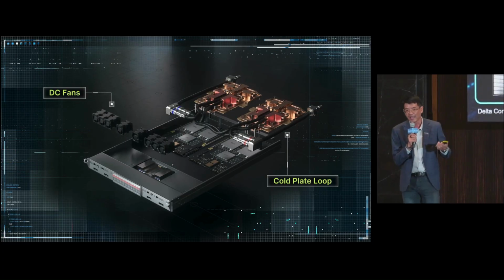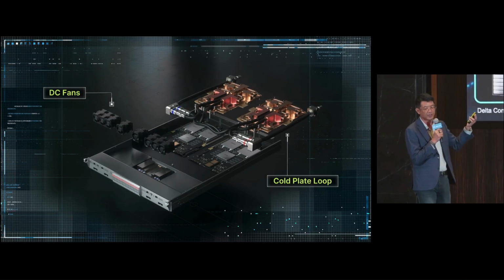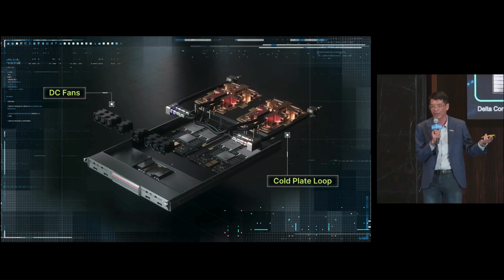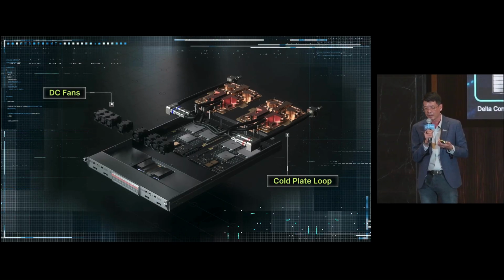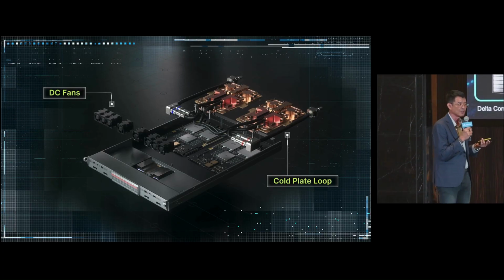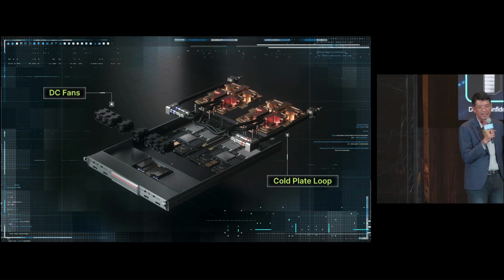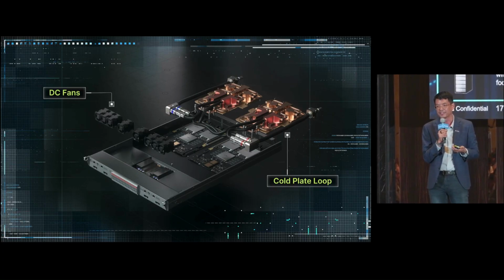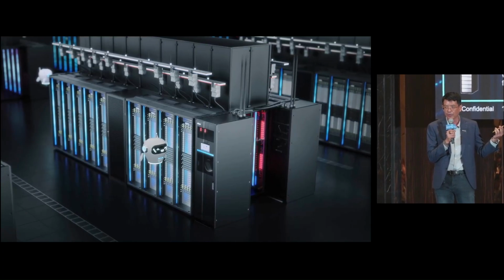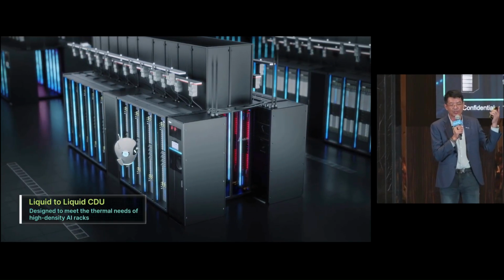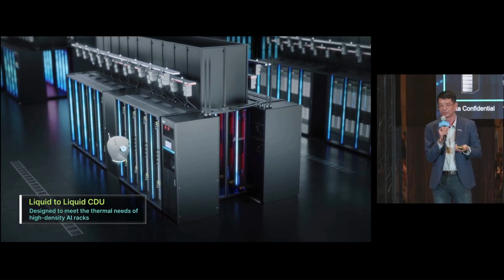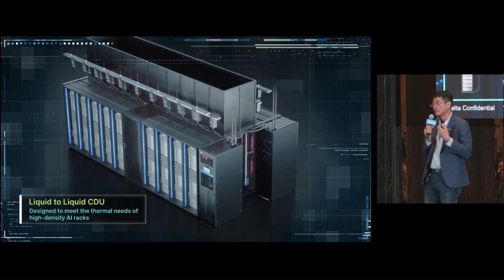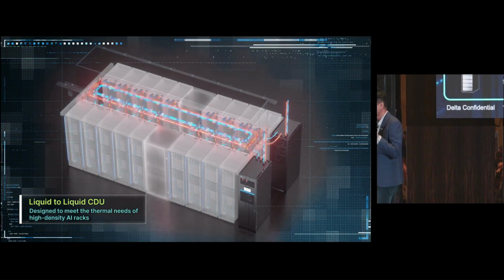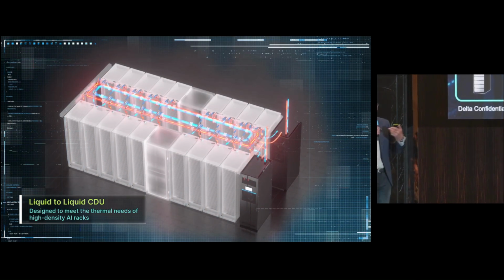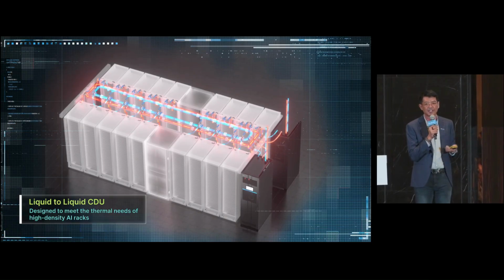Inside this AI pod, we implement a liquid-to-air cooling solution as well as the DC sidecar solution, so you can still use AC voltage to supply high voltage DC. We can also do hybrid air and liquid cooling using in-row modular CDUs — if your fan wall cooling capacity isn't enough, you can take more heat out with the CDU.